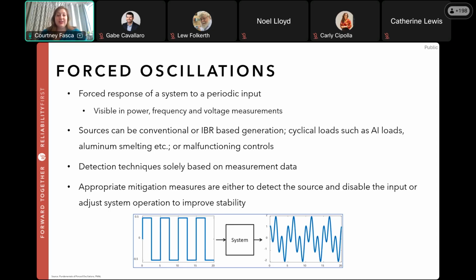And unlike transient oscillations, these oscillations typically persist until the forcing input, the cause, disappears or is removed from the system. To compare that, transient oscillations are kind of like a pendulum that swings until it stops due to the air resistance. Meanwhile, forced oscillations are like a child being pushed on a swing, maintaining their motion until you stop pushing. Detection-wise, forced oscillations are purely based on measurement data. Tracking with PMUs is critical to this. If forced oscillations are not suppressed or ended, they can cause equipment fatigue, damage to rotor shafts, poor power quality, and even generator tripping.